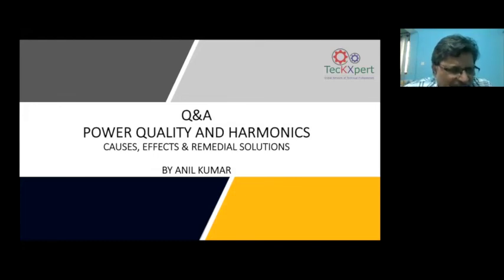So I would say that we should measure this EMI and the harmonic impact without the filter, and then with the filter. By looking at the waveforms, we have to see whether we can do some readjustments or redesign of the filter, because whoever has supplied you that EMC or passive filter, I'm sure they probably have that data and can redesign it and make it work for you.